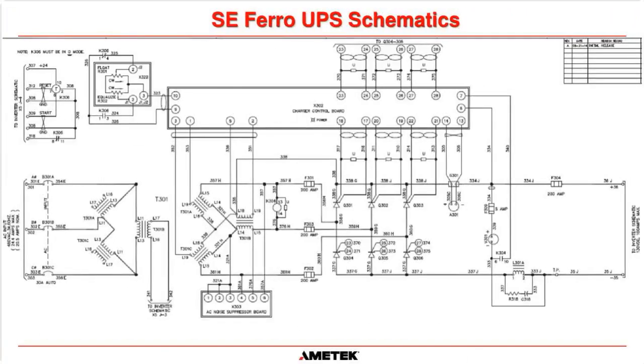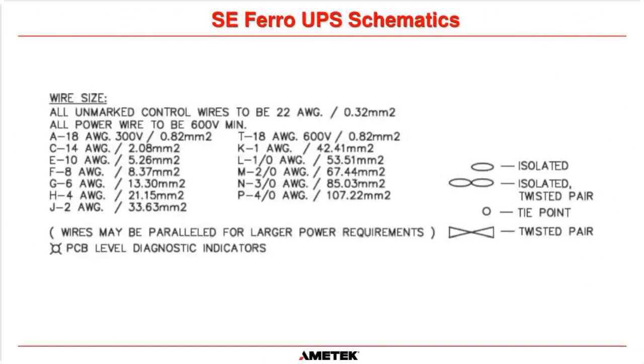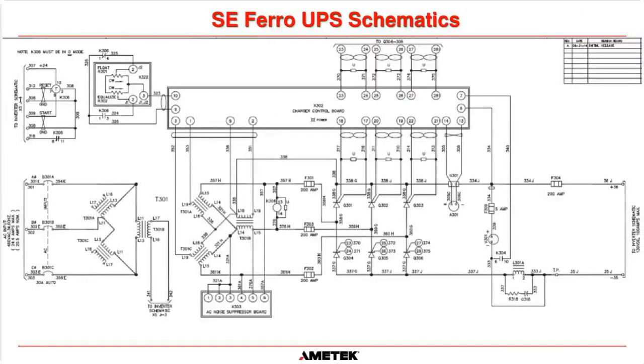So if I go onto this page here, for example, you can see cable number 334, and then it says J. So the cable number is 334, but the J is saying it's a number 2 cable. I hope that's clear. Now, if this was a larger system, say a 50 kVA system, just for example, that may say 334JJ. So if we have JJ, that means there are 2 number 2 cables in parallel. And you can see this wire here, 338, does not have a letter after it.